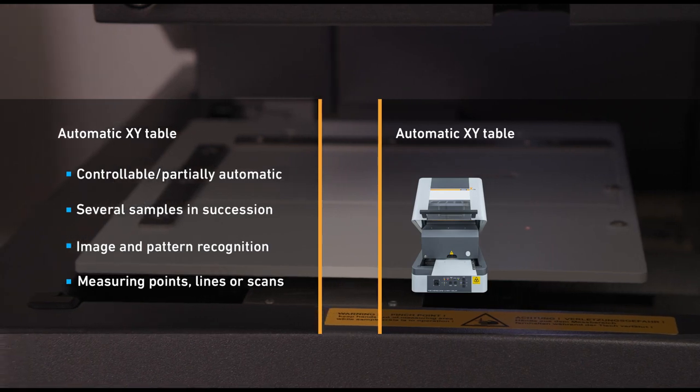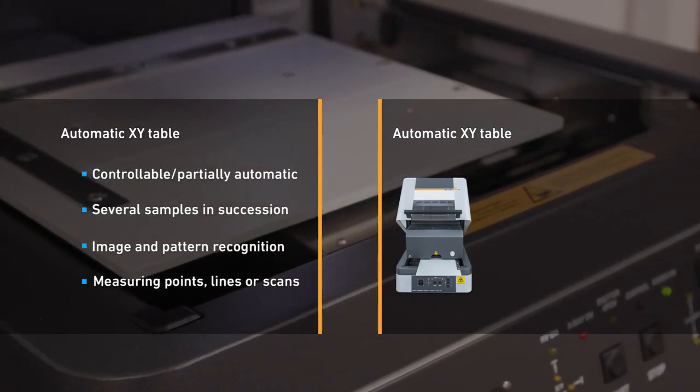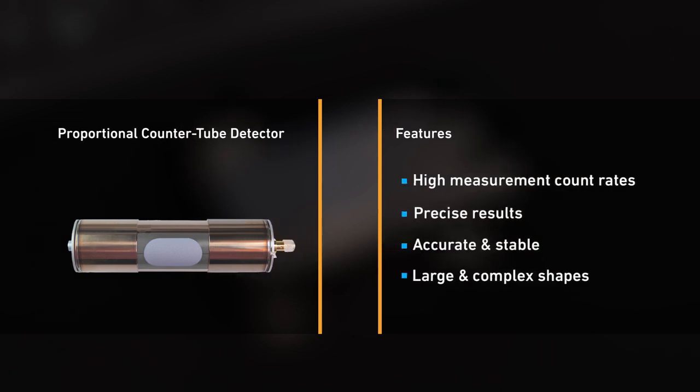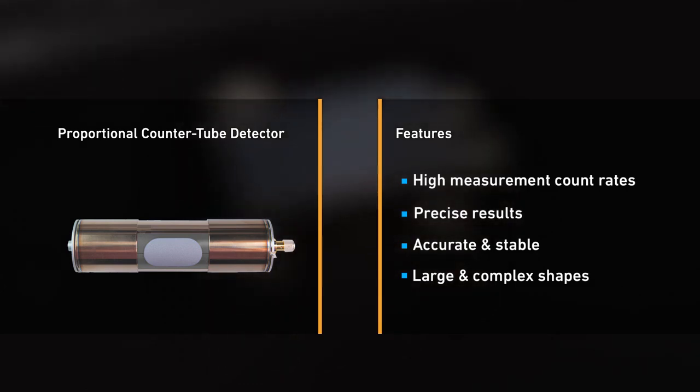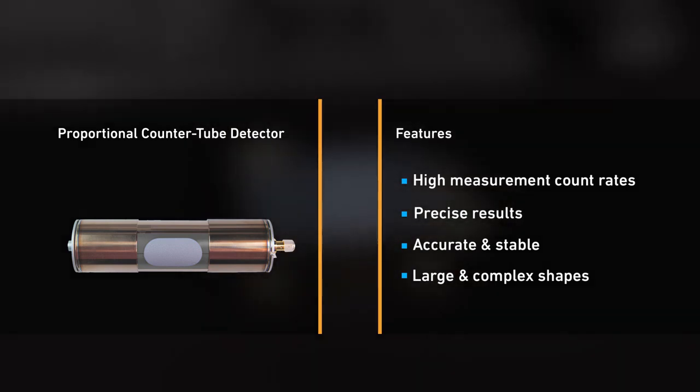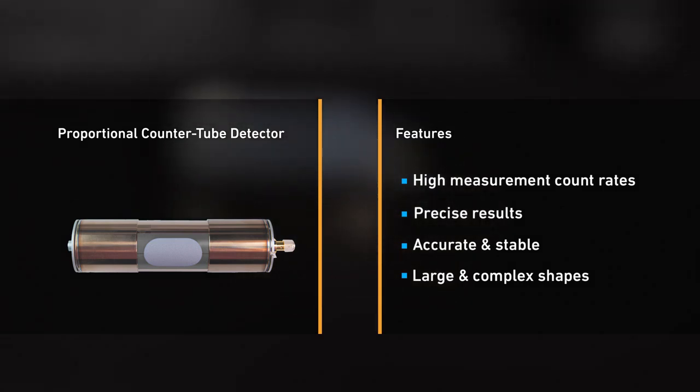The instrument benefits from a state-of-the-art proportional countertube with a large X-ray capture area producing high X-ray spectrum count rates and excellent precision. This type of detector can be distant from the measured surface to accommodate complex shapes, which is a significant advantage over silicon-based detectors that must be close to the measured sample to be effective.